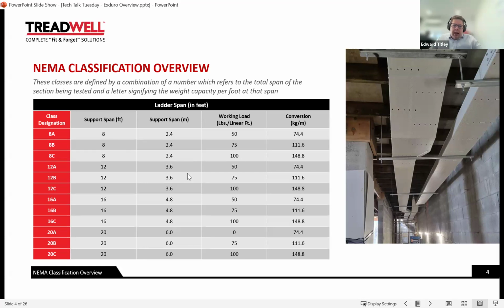And then class A, B, and C have a pounds per linear foot working load, which we've converted here into meters. So class A is 74.4 kilos per meter as a working load. Class B is 111.6 kilos per linear meter, and class C is 148.8 kilos per meter. And once again, that applies to any cable ladder or cable tray product, whether it's FRP, stainless steel, aluminium, or any other material. So the NEMA classification applies to any product.